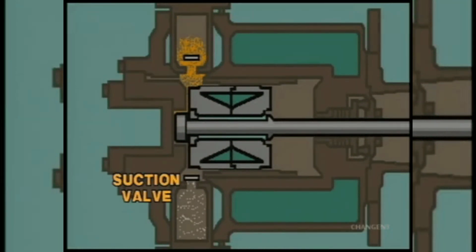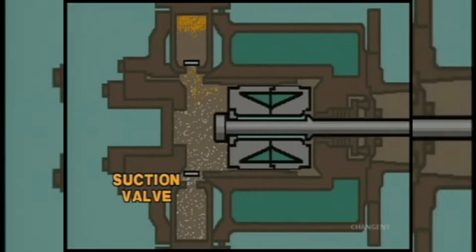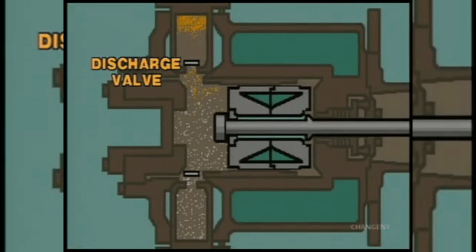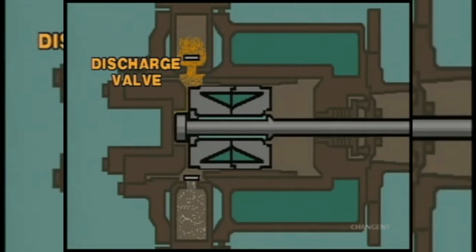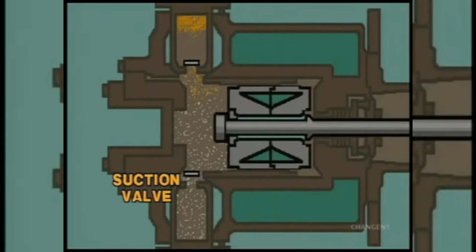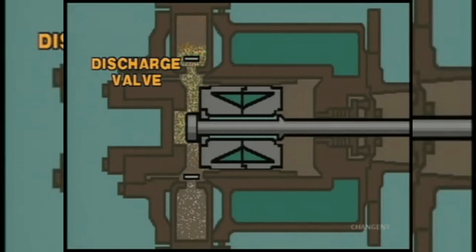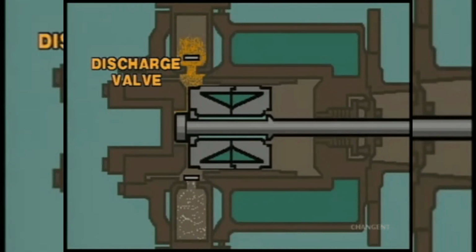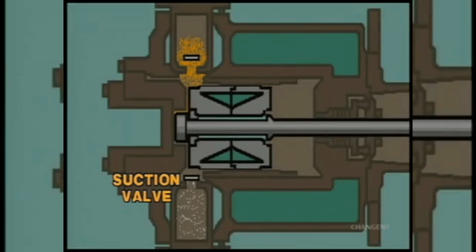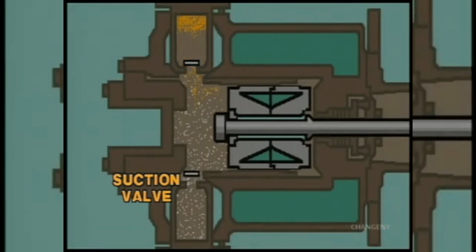Pulsation control. Pulsations generated by a conventional reciprocating compressor have to be damped, attenuated using pulsation filter bottles, orifice plates, choke tubes, and/or Helmholtz resonators, all of which add cost and complexity and reduce compressor efficiency. The LMRC will operate at very low speeds. As a result, pulsations are expected to be much less problematic, and most of the above-mentioned pulsation attenuation devices should not be necessary.